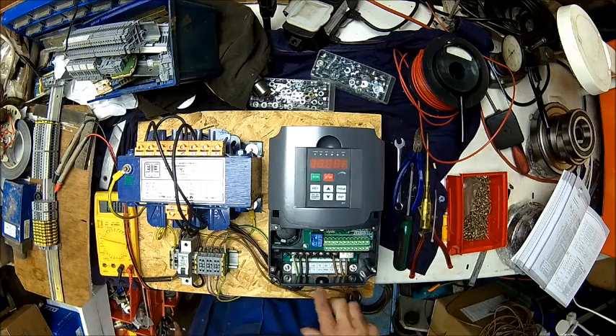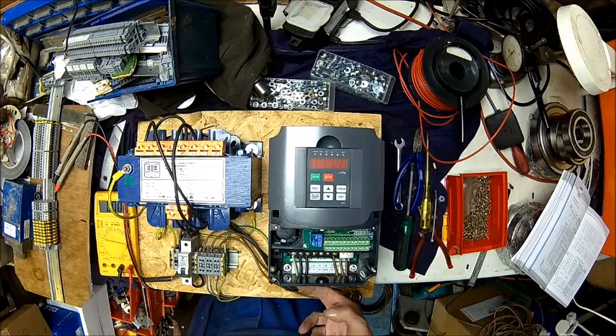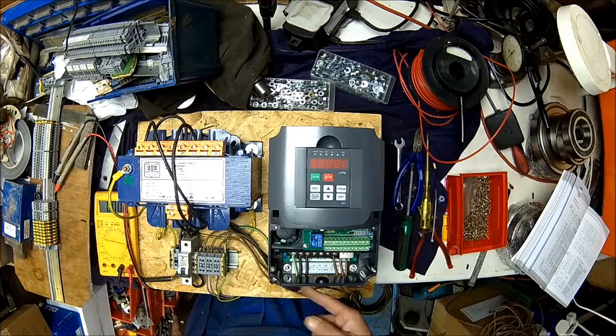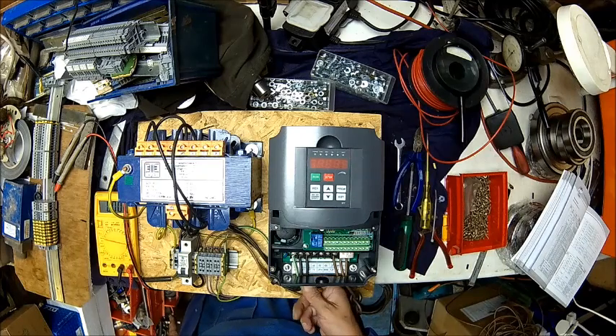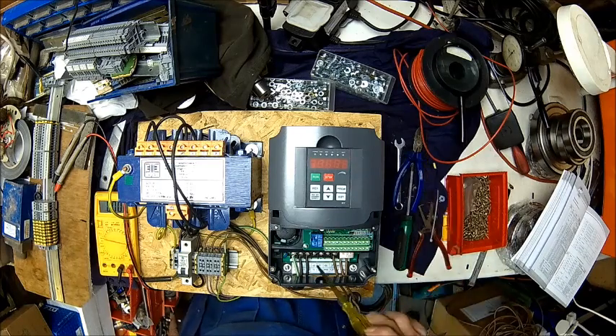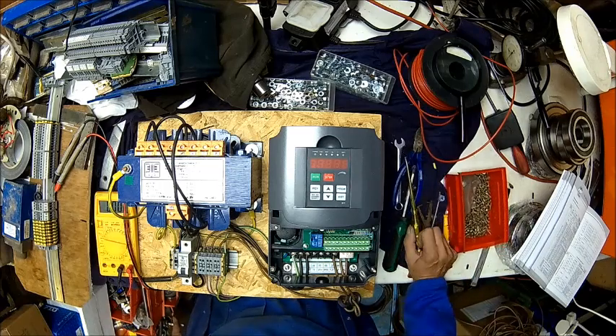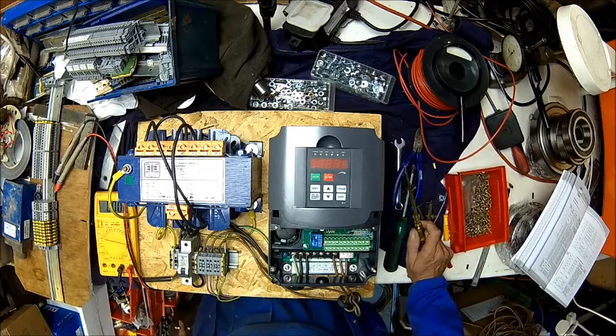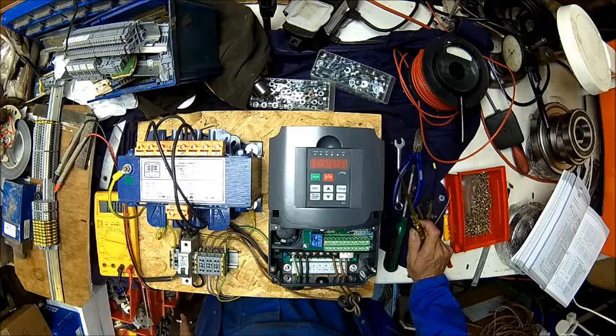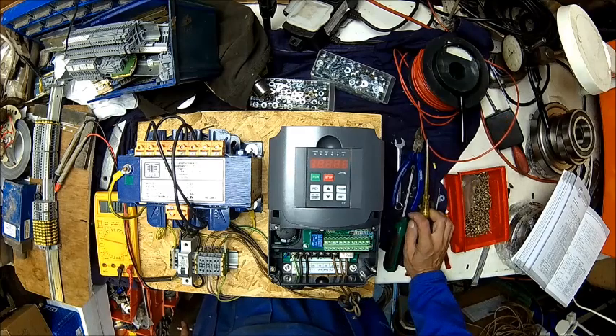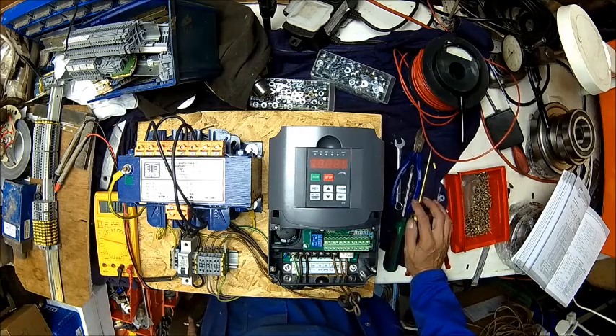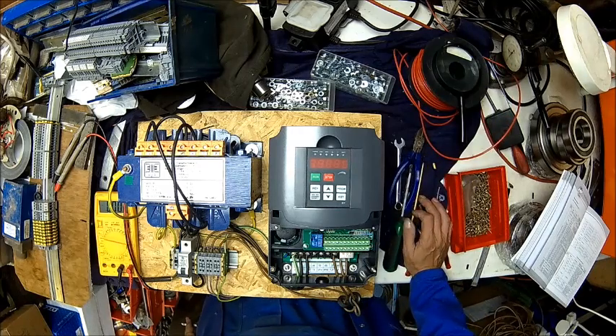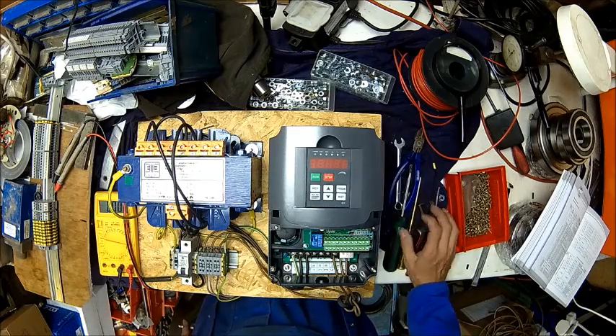It's somewhere in the middle, because we basically feed neutral 0 volts and 400 volts single phase into that inverter. So the third terminal stays free, because we only feed it with single phase. That's another reason why you need a slightly overrated inverter, because the capacitors are designed for 3-phase, where the intermediate voltage, the bus voltage, is a little bit higher than with the single phase supply, because the ripple is 150 Hertz instead of 100.